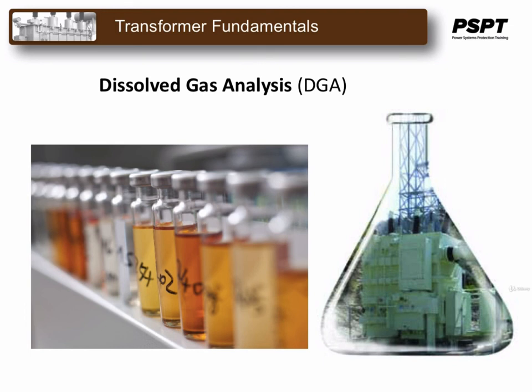DGA usually consists of sampling the oil and sending the sample to a laboratory for analysis. Mobile DGA units can be transported and used on site as well. Some units can be directly connected to the transformer. Online monitoring of electrical equipment is an integral part of some of the transformers.